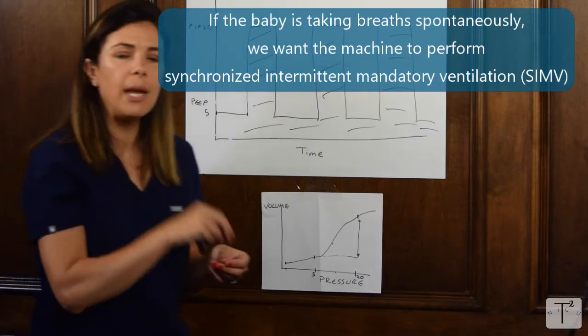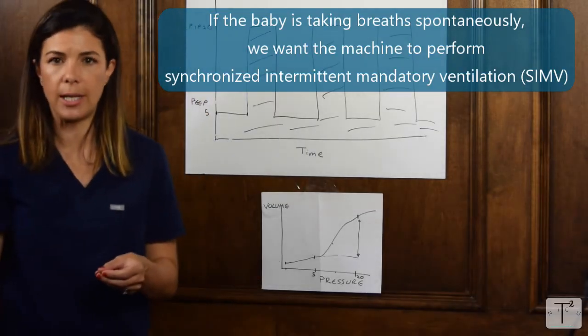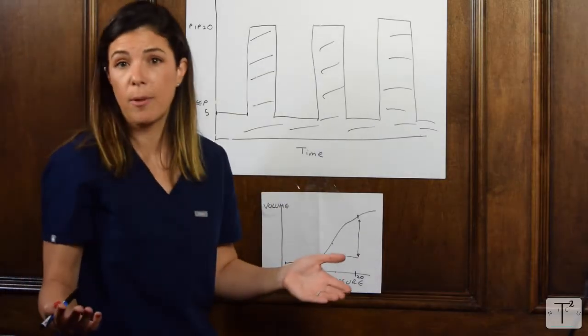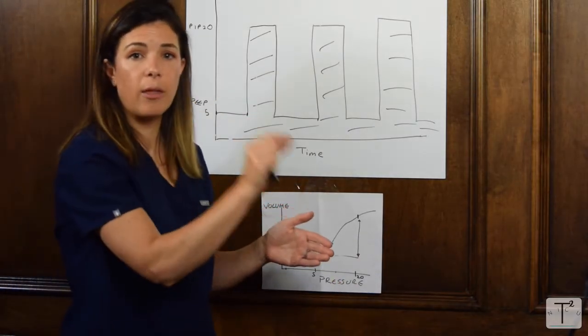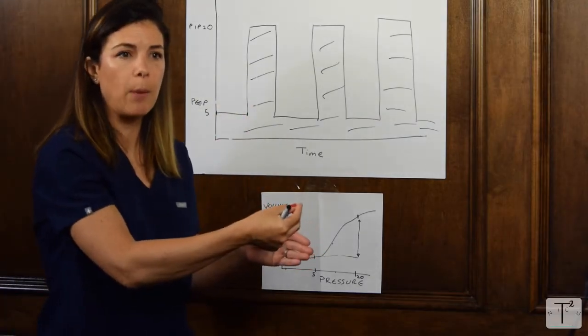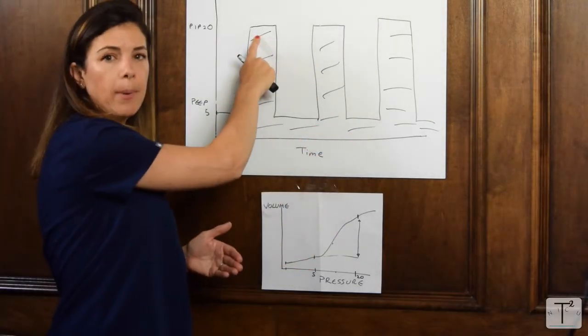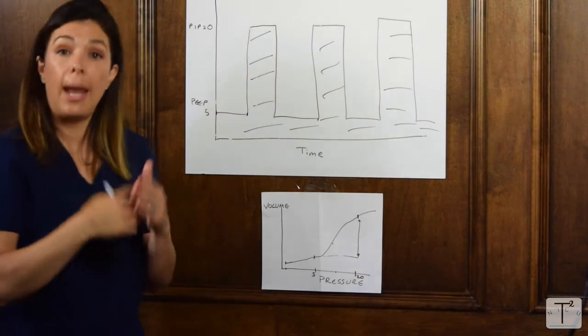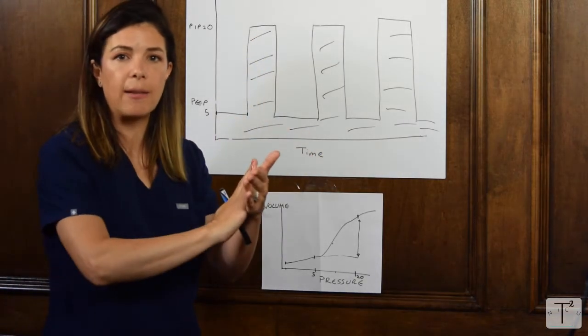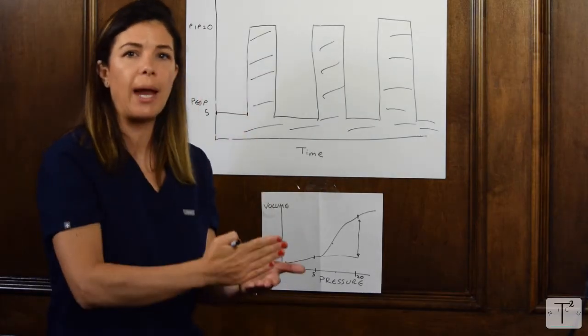What we really do is synchronized intermittent mandatory ventilation, which means that if the baby breathes 20 times a minute, even if you set the rate at 30, for those 20 breaths, the machine will recognize when the baby's about to take a breath, and then give it the full PIP. In that situation, the baby is not always going to be fighting against the machine. It might not be exactly two seconds. It could be at one and a half seconds, and then three seconds. But the machine will wait for the baby to take a breath, unless it's lasted too long, and then it will force a breath.